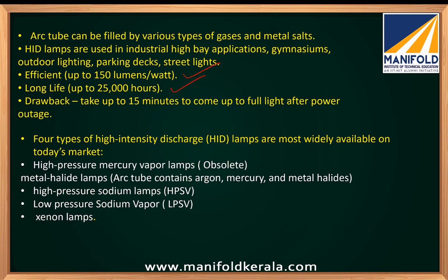They have a long life, around 25,000 hours. The drawback is that they take some time to reach complete illumination, usually 5 to 15 minutes after power up. So once the power is gone, to start them again, it will take some time.